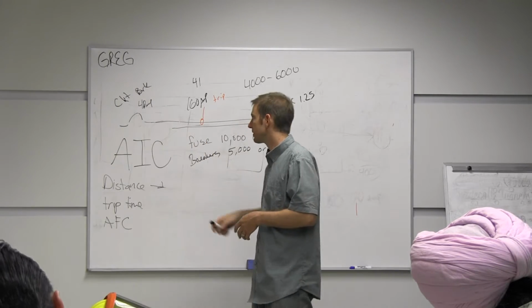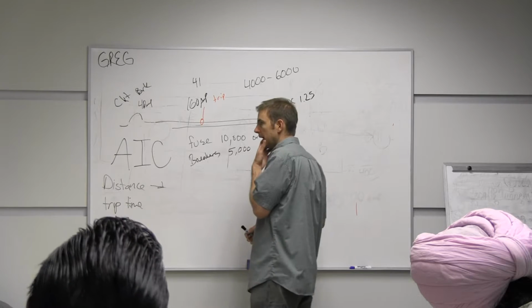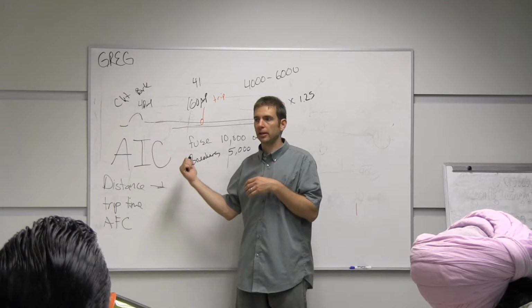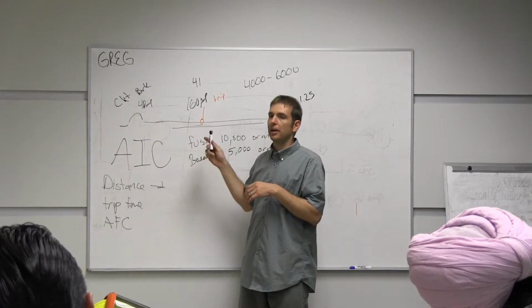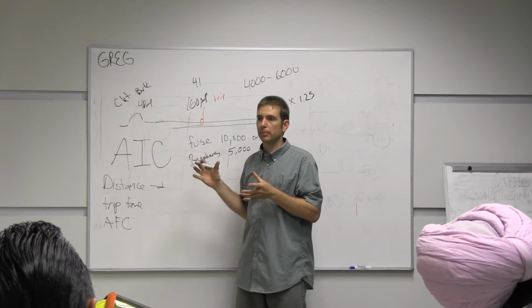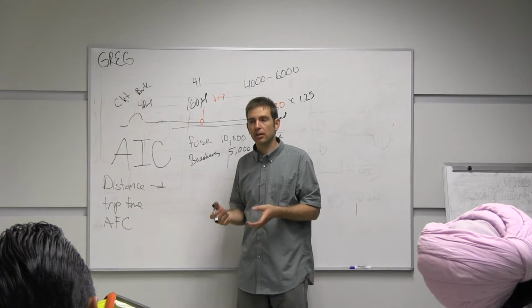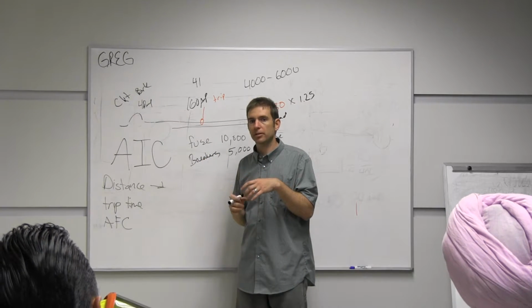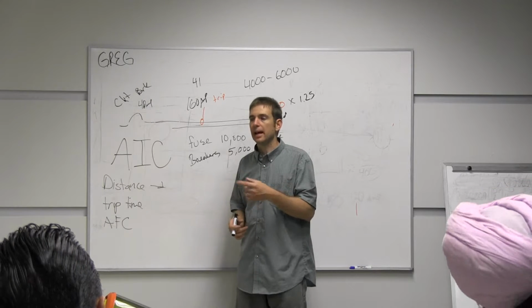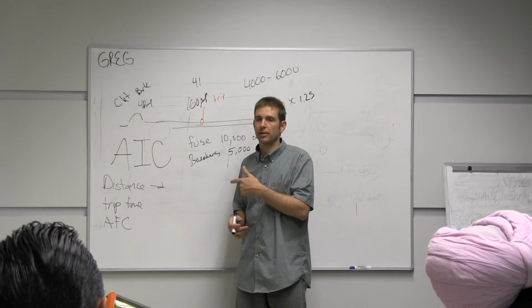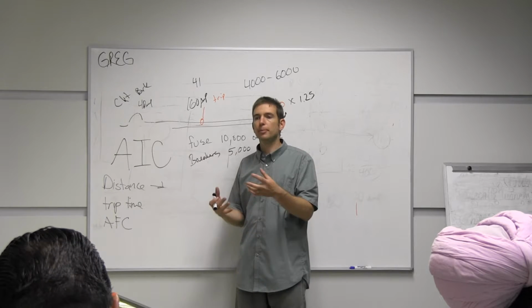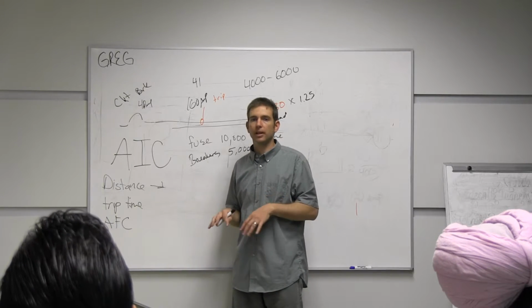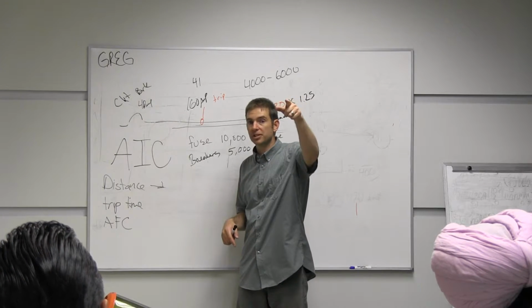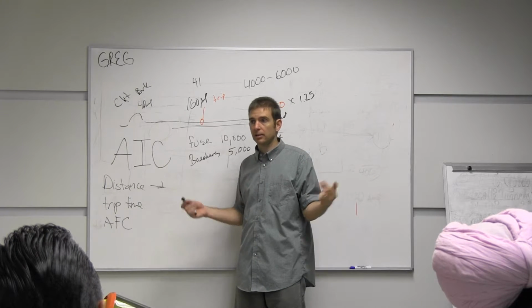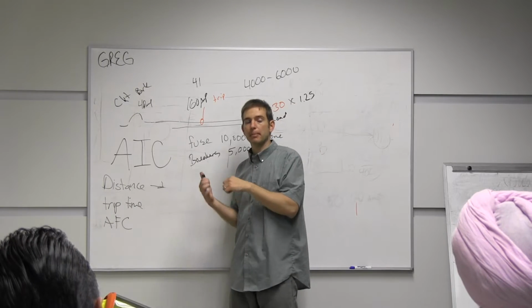This is what happens. This is how it gets screwy. You have a panel in the next room here. It's a 100,000 amp AIC panel. It's a very expensive panel. It's got heavier duty breakers. They're thicker. They're more expensive. That panel fails for one reason or another. It's got some bad buses. So you remove the panel. You start looking online for a new one, or maybe you have a new one in the shop. You're like, hey, here's another panel. Let's stick this thing in here. You put that panel in.